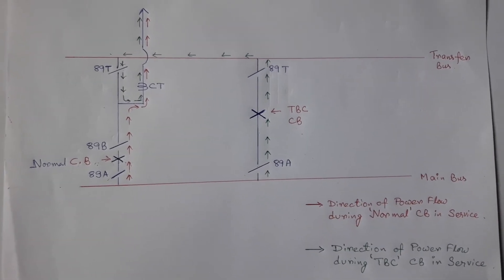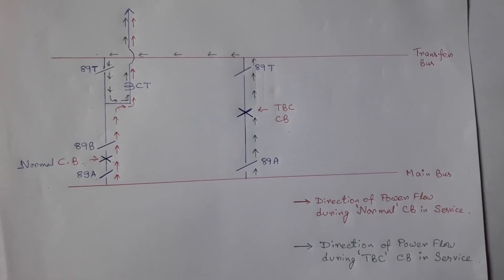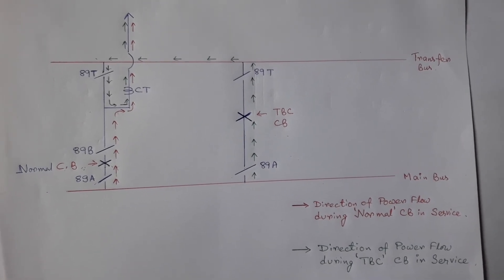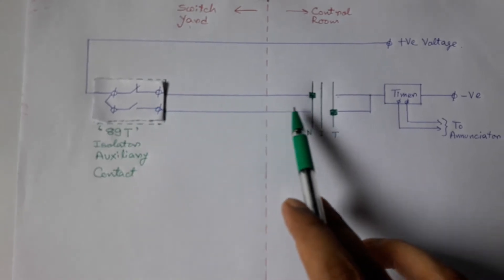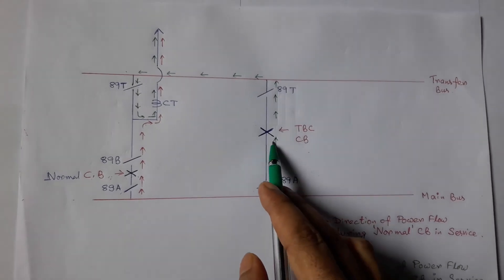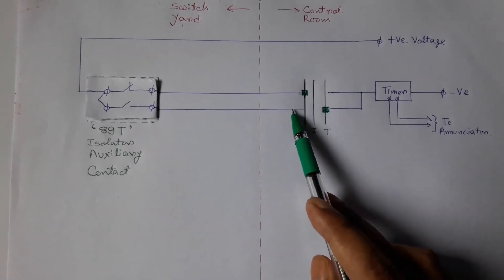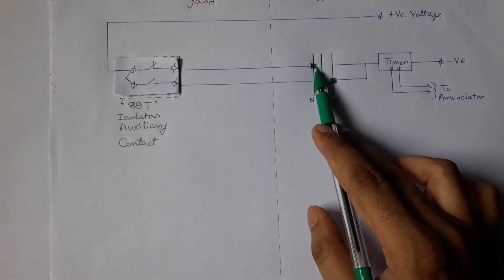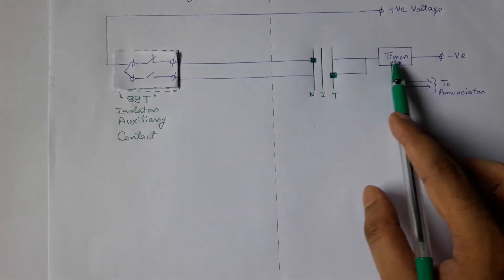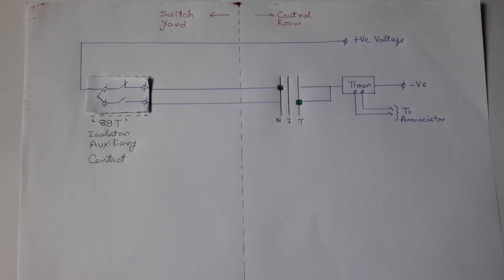But when the normal circuit breaker becomes defective and the load is diverted to the TBC circuit breaker, from the direction of power flow as shown in green, we can see that the 89T isolator is closed or in use. So the contact configuration of this 89T isolator will change, and in this case positive voltage will come to this terminal. When the TBC circuit breaker is in operation, our goal is to trip this TBC circuit breaker only. So we will put this switch in transfer position, and as there is no voltage, there will be no audible annunciation. But if accidentally we put this switch in normal condition, then this positive voltage will actuate the timer and after a predefined time delay, there will be an audible annunciation that something is wrong.